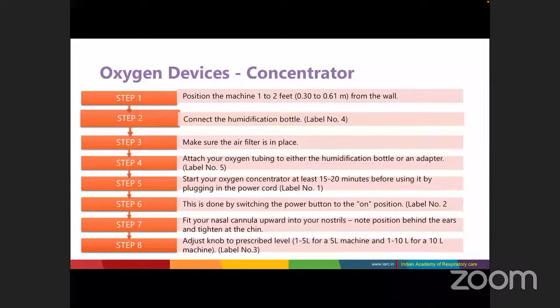First of all, position the machine 1 to 2 feet away from the wall. Second, connect the humidification bottle as labeled in the figure, number 4. Make sure the air filter is in place. Attach your oxygen tubing to either the humidification bottle or an adapter, which is labeled as number 5. Start your oxygen concentrator at least 15 to 20 minutes before using it by plugging in the power cord and switching the power button to the on position. Number 2 shows you the power button. Once you plug in, just turn it on.